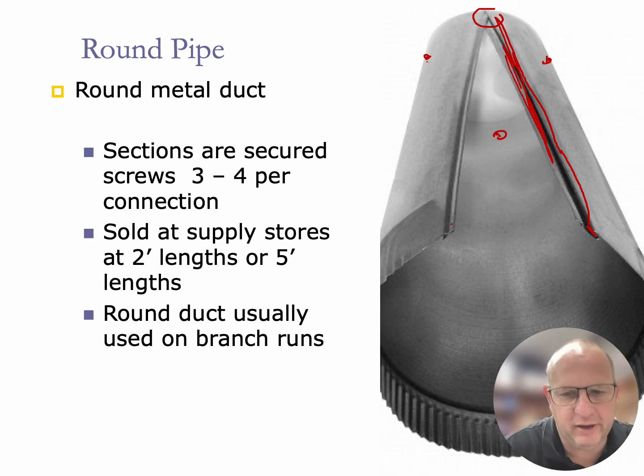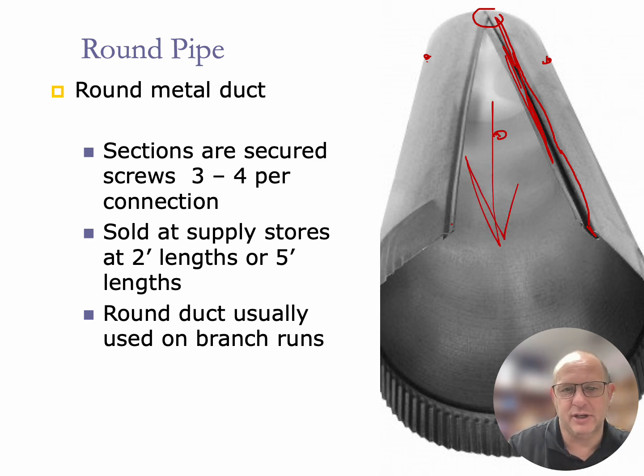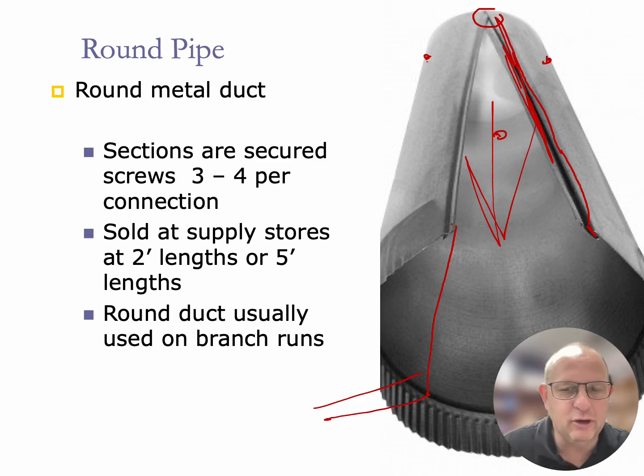Just one more thing in particular that we need to understand about our metal pipe as we're running. Our takeoffs are going to have our crimped ends, and we're going to want to continue that crimp in the direction of the airflow. So the airflow is going to be flowing down this direction within our pipe, so our crimped end is going to be in that area. So as the air is coming down, it doesn't find an easy way to flow out of the ductwork because we have installed it in the correct position. It's just going to flow through and then create that static pressure that we want, the velocity pressure that we want, and the total pressure within the duct system that we want for it.